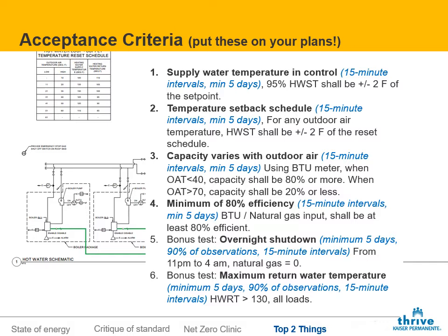Some of you may be thinking that if we open a building in the summer, this won't work, right? You can't trend a boiler system in the middle of the summer and expect it to work out right. But I would urge you to look at the list again. These 6 statements should be true all year long. These statements should be true in an unoccupied building or an occupied building. They should be true really no matter what condition we throw at the system. And that's one of the biggest lessons that we've learned in doing this on our buildings.